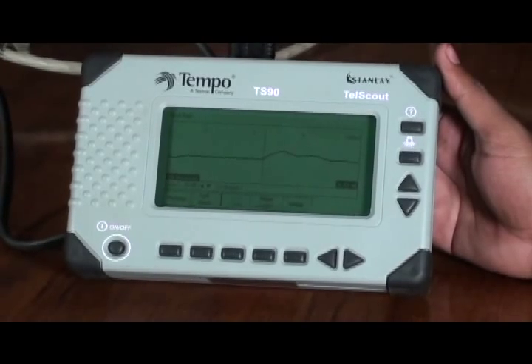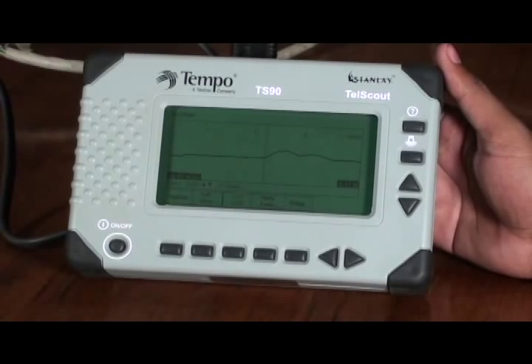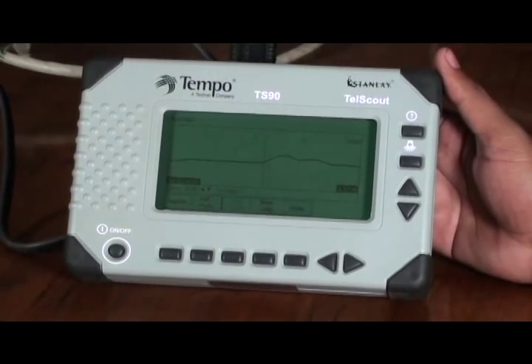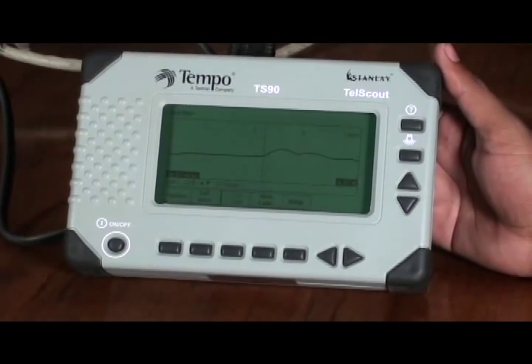This means that the machine is now set to measure the exact distance to the fault of identical type of cable for all times to come, as the velocity propagation has been set for this type of cable.